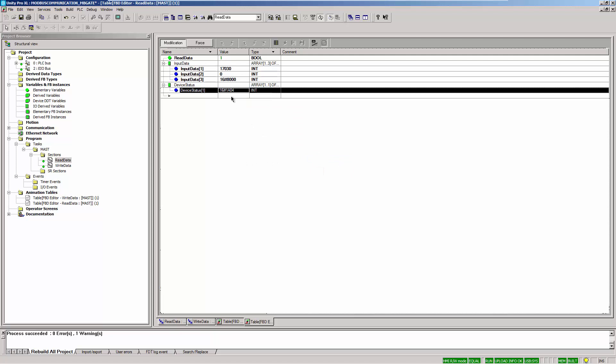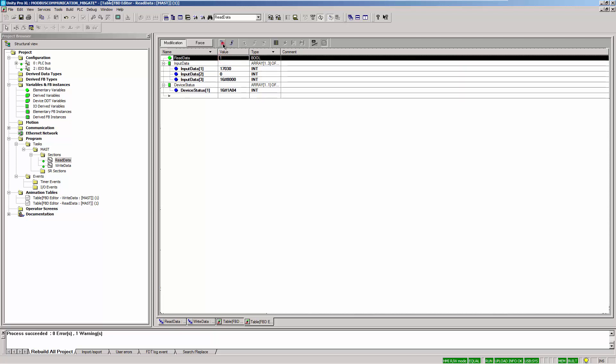The high byte of the status information is the so-called life sign. The value is incremented by 1 with each successful reading of input data from the device. The low byte describes the operating state of the device — the value 4 means that the device is in cyclic data exchange. The high byte of the third register of the input data contains its status; hex 80 means good. The first two registers of the input data correspond to the value. Repeated reading shows that this data changes.